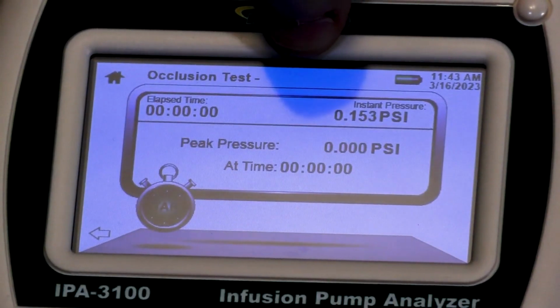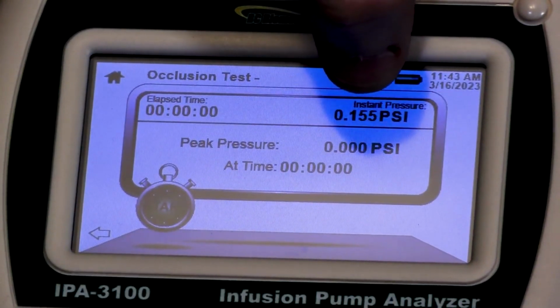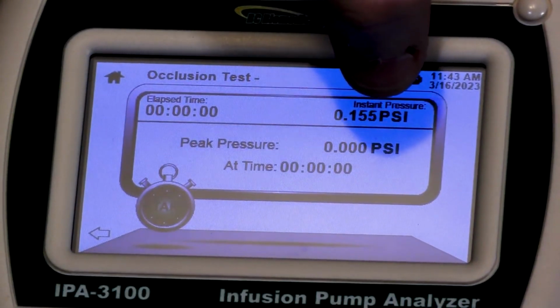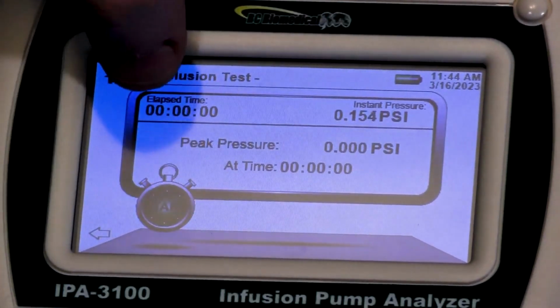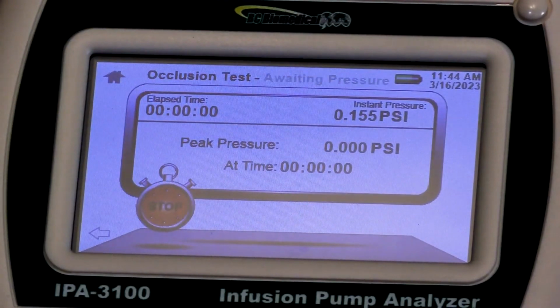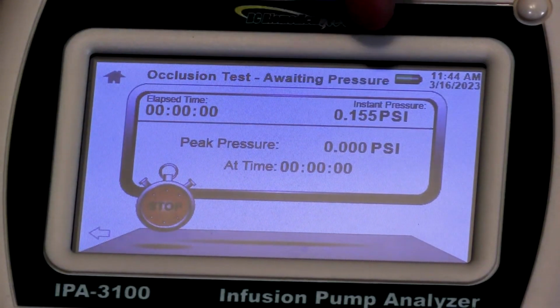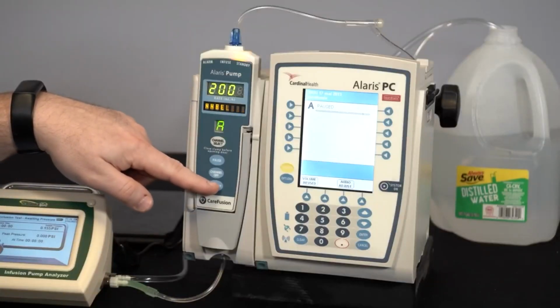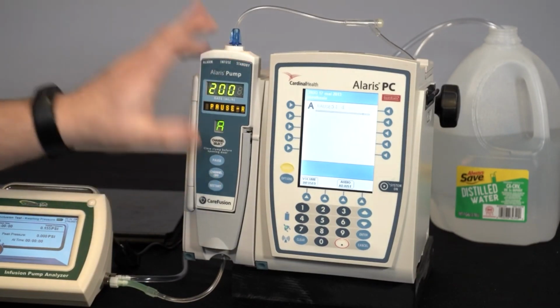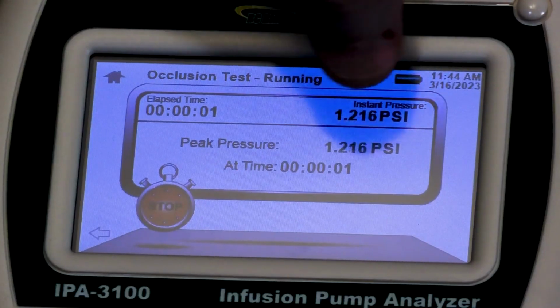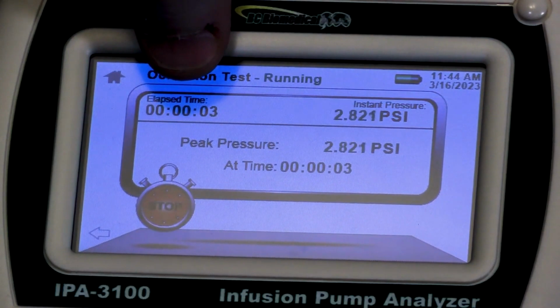I can see here that it's ready to start. It's giving me the current pressure that's in the tubing right now. And again, the timer hasn't started because I set it to auto. When I start the test, now it's ready. It's waiting for the pressure. As soon as it sees pressure from the pump, I'm going to restart the pump here. It's going to start flowing. As soon as it saw pressure, it started measuring time.